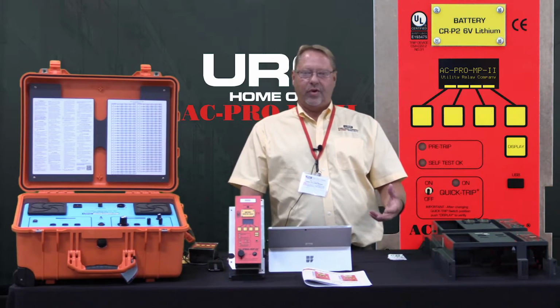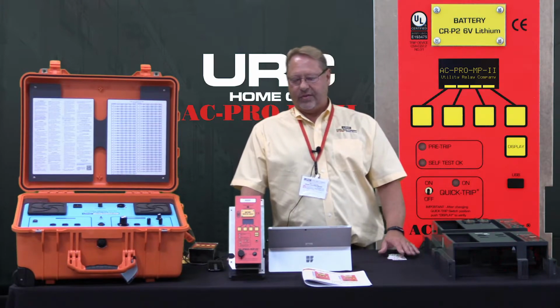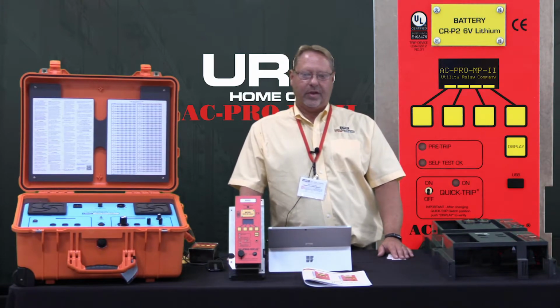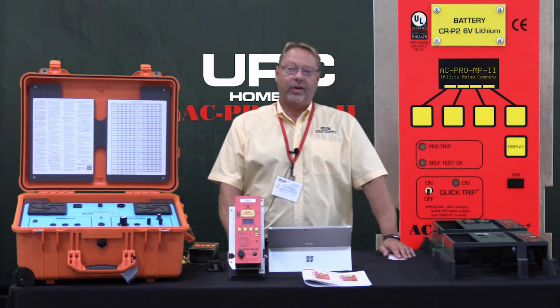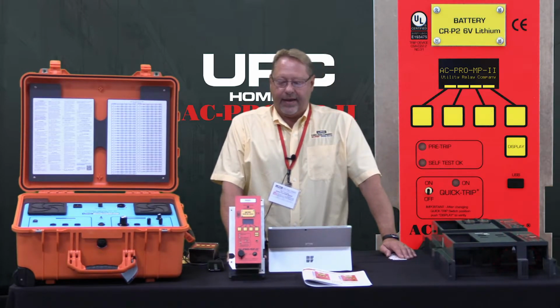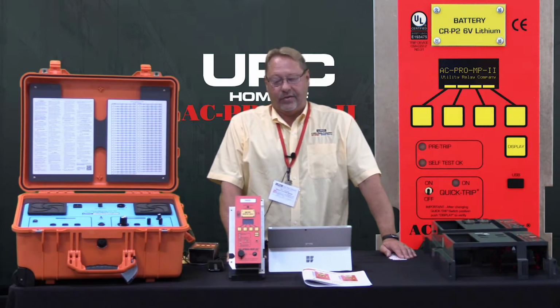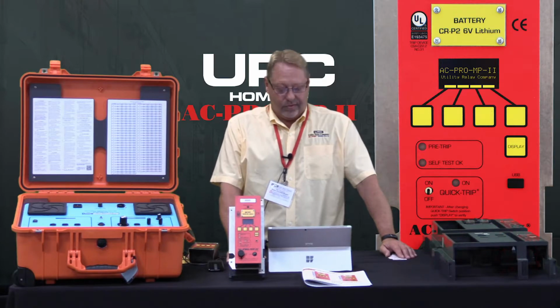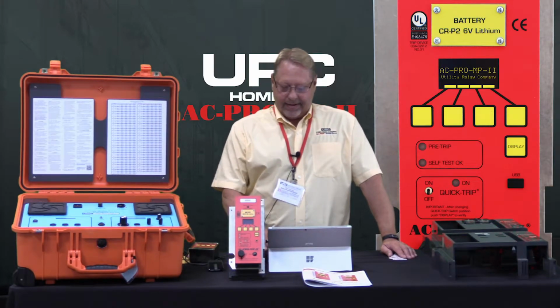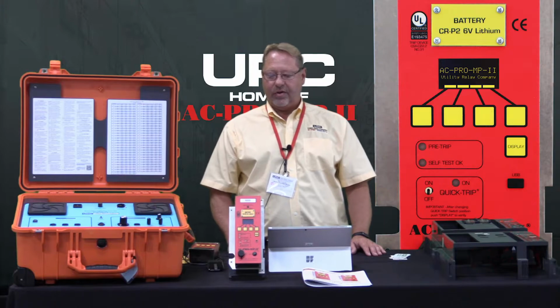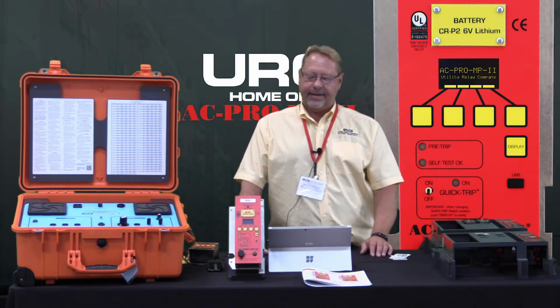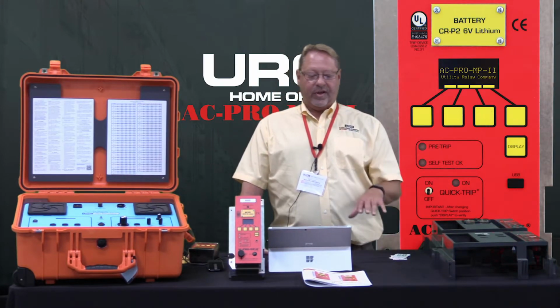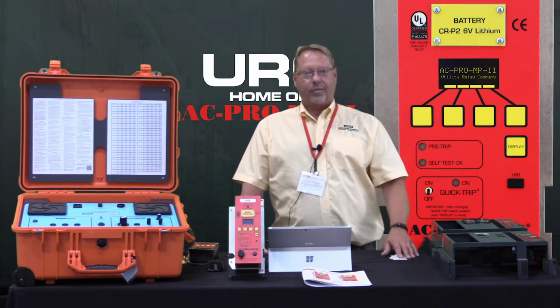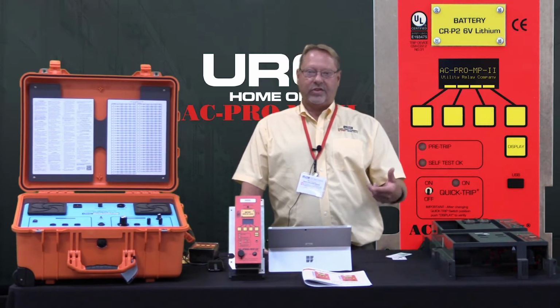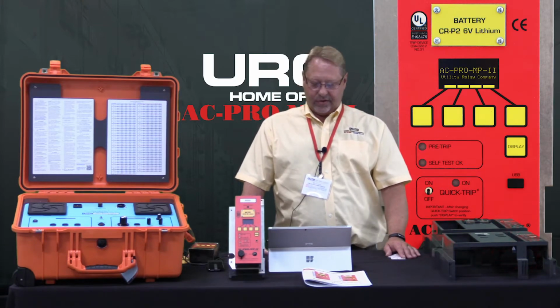Energy metering is important for efficient operations of facilities, so the MP2 will do kilowatt, kVA, and energy metering along with power factor, and communications was also added. So the MP2 speaks Modbus RTU communications. The trip unit has the exact time current curves of the STR trip unit. So you can just replace any of the STR trip units with the AC Pro MP, and all you have to do is select what trip unit you're replacing on the unit.